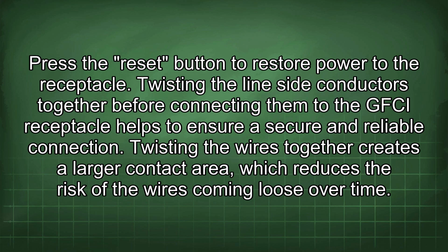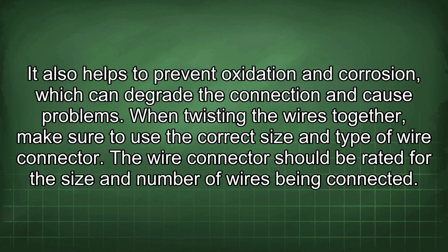Twisting the line side conductors together before connecting them to the GFCI receptacle helps to ensure a secure and reliable connection. Twisting the wires together creates a larger contact area, which reduces the risk of the wires coming loose over time. It also helps to prevent oxidation and corrosion, which can degrade the connection and cause problems.